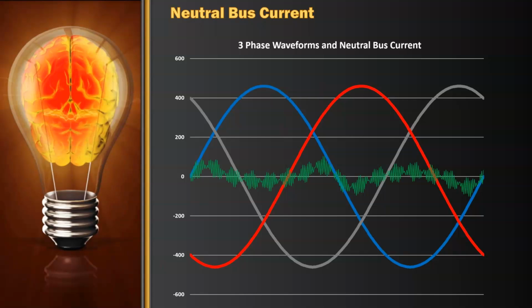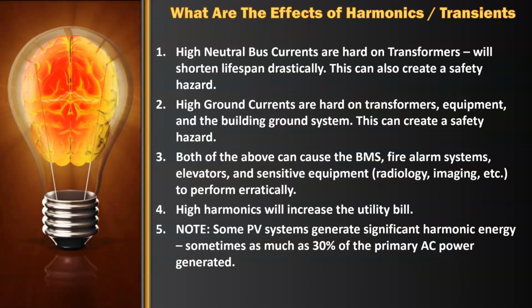Very hard on the transformer. So high neutral bus currents are hard on transformers. They'll shorten the lifespan drastically. Can create a safety hazard. High ground currents, same thing, bad on transformers. Definitely going to make a safety hazard. Both of those will cause problems with the BMS because the BMS is getting these weird voltage signals and the ground is not very stable and things like that. So the BMS, fire alarm, elevators, all that stuff that requires a reasonably good sensitive ground is now going to have a floating ground, and it's going to tend to operate erratically. Does increase the utility bill.